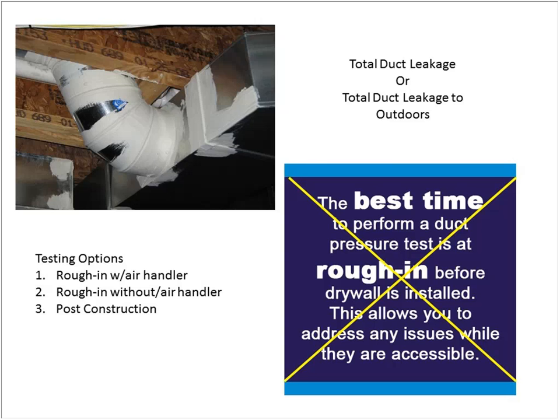We had a home that we tested at least half a dozen times. The total leakage was about equal to the total output of the furnace, about 1,500 CFM at 25 pascals. We never could isolate that leakage in that environment. So we went back in the spring after the house was completed, and we tested total leakage to the outdoors, and it was well within the limits allowed. But total leakage, we could never get it down to where it needed to be.